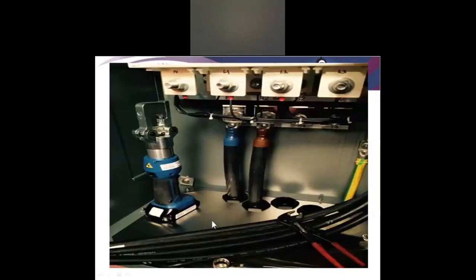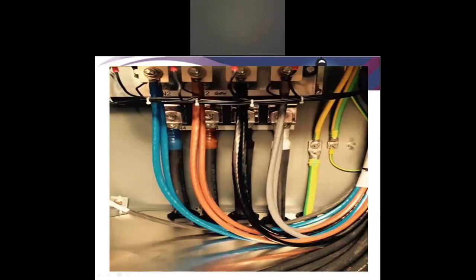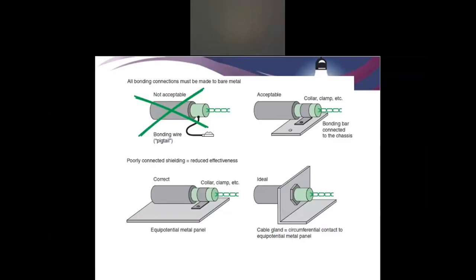It's in cable, in panels, in new panels, how we use it. There will be a separate wire provided for earthing. This is going to connect it to the earth mat, and this wire is for making this metal part at the same potential as the earth. These are live things to be connected, but again we should not forget to connect the earth wire to the metal part, so that this panel should also be earthed. It's a universal rule that electrical equipment connected to metal parts should not be left unearthed - you have to connect all metal parts to earth.